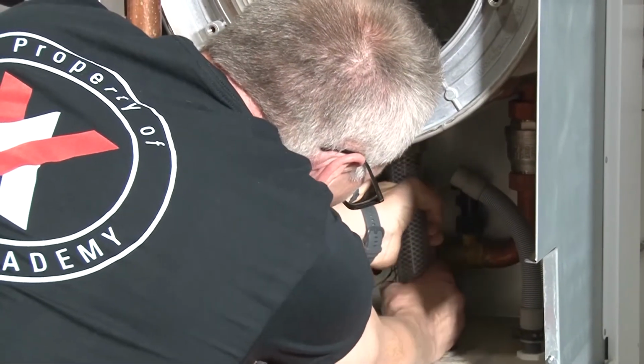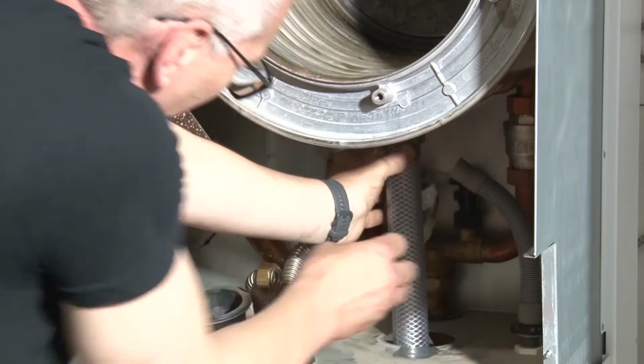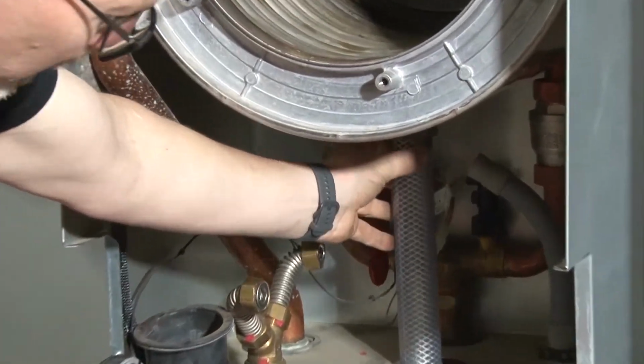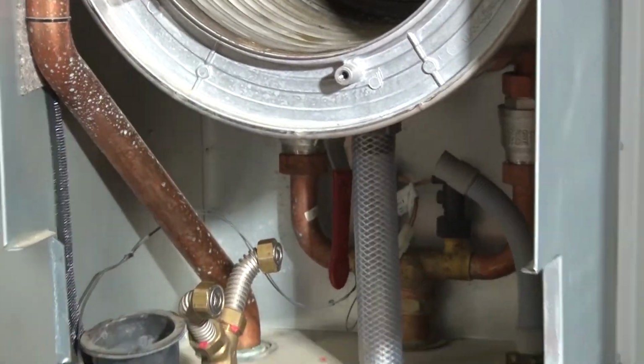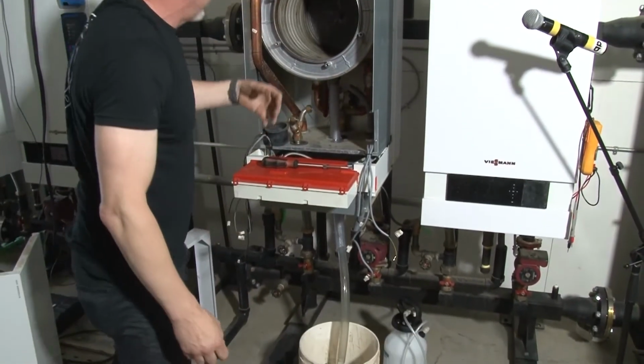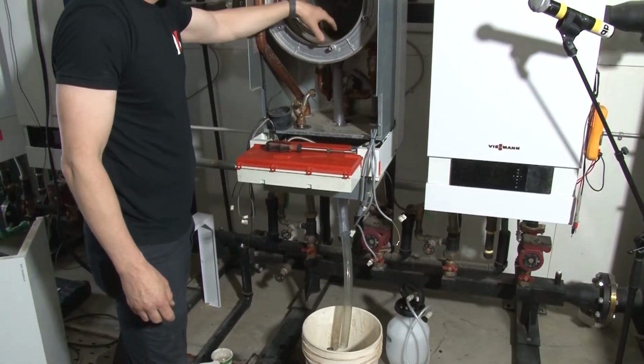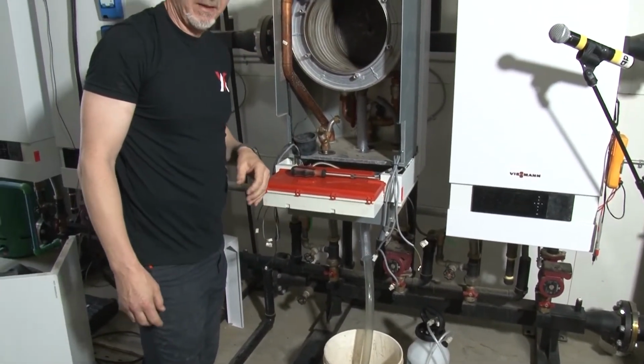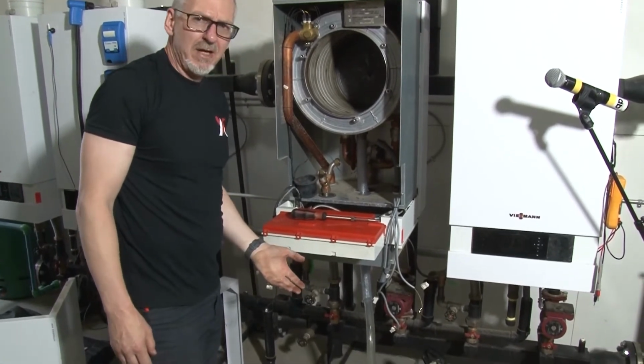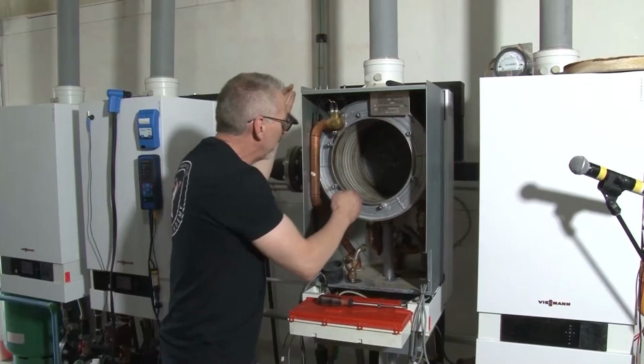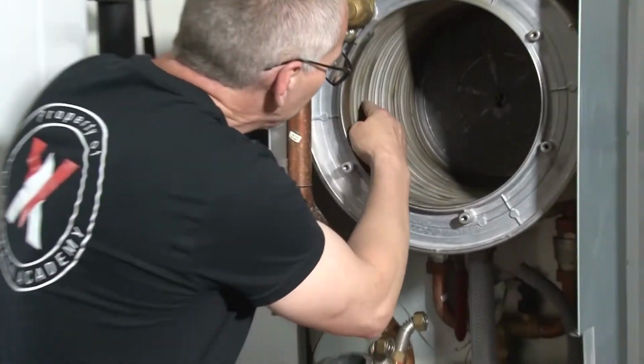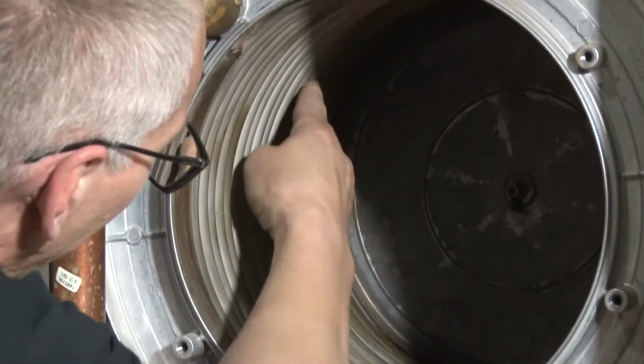And it actually makes a very nice tight fit onto the bottom of the boiler here. And I can have it right down into the bucket here. So when I'm doing my cleaning and service and stuff like that, all that stuff is getting flushed down the bucket. Depending on the chemical you're using, you may not want to flush that down the drain. If you look inside here a little bit, you'll notice that there's some staining up in this area.